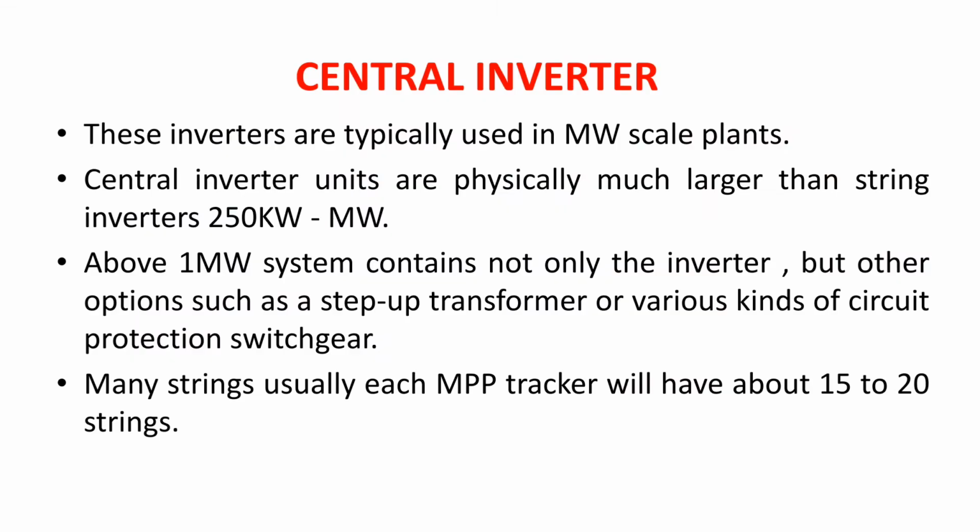Friends, for above 1 megawatt systems, sometimes these central inverters don't come alone. They come with a step-up transformer and other types of protection switchgears, and all this is housed in a single box, which is a complete central inverter system. And as these central inverters are big systems, the MPPT trackers will have more strings, like 15 to 20 strings for every maximum power point tracker, MPPT tracker.